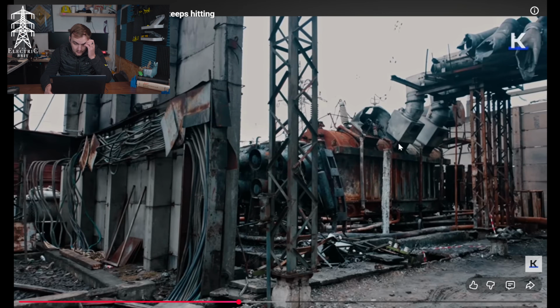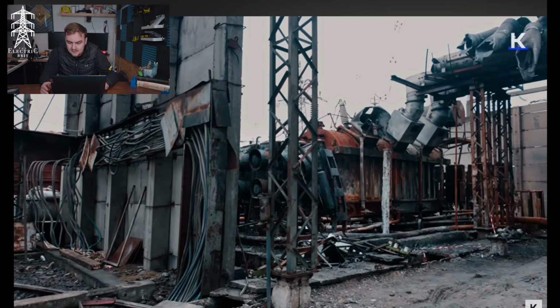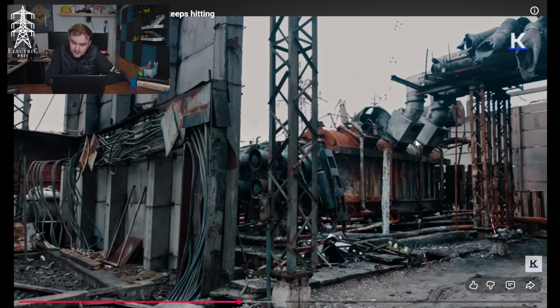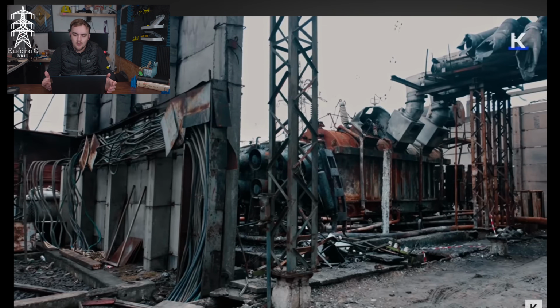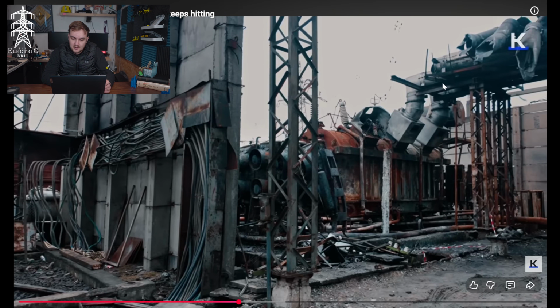Talking about those ducts, or gas insulated bus bar as before, that's what we're seeing here. Looking up to the top right of the picture, these ones go up and across - chances are this is a separate bus duct above it, or a gas insulated bus bar going across the top, probably into this bay here where there'll be another transformer. That's the benefit of having these ducts or gas insulated bus bars - you can have them really close together, right on top of each other, and they won't arc across.